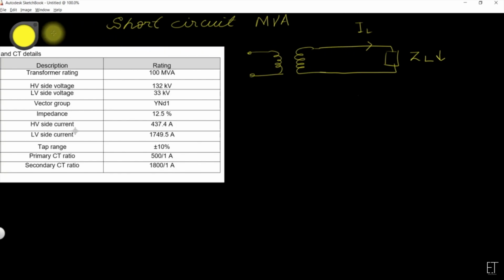But what happens if there is a fault on the line? For example, if there is a phase to ground fault on the line, then you can easily see that the load impedance will be completely bypassed. If the neutral of the transformer is also grounded, the current will flow back to the winding and this impedance is completely bypassed. So this is the loop or the path of the fault current IF.